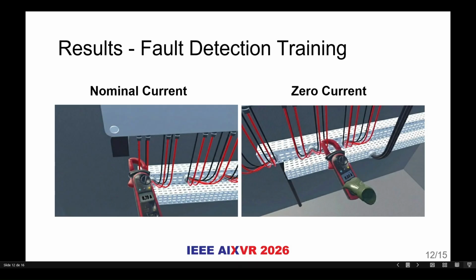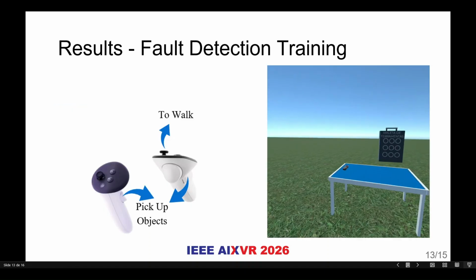However, on the right, when the user measures a different string, the reading drops to 0 amperes. This indicates a fault, such as a disconnection or a damaged cable. The important point here is that SolarVirt guides the user through this process. The simulator teaches the student to interpret these values, helping them understand why the current is missing and how to identify the root cause of the problem.